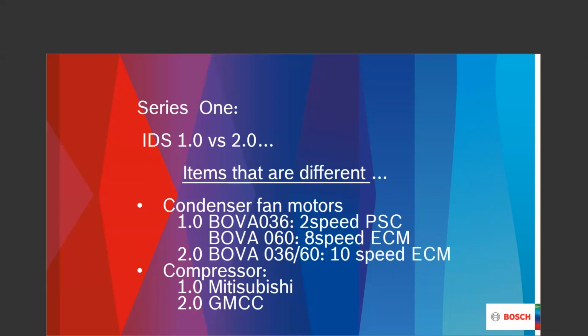So we have that old capacitor that we may have felt real familiar with, and we see that. In the BOVA 60, we see that the 1.0 now grows into an 8-speed ECM motor. And then the 2.0, both the 36 and the 60, have a 10-speed ECM condenser fan motor. Differential in the 1s and the 2s at that point in time: the compressor on the 1.0 is a Mitsubishi. The compressor on the 2.0 is the GMCC branded compressor.